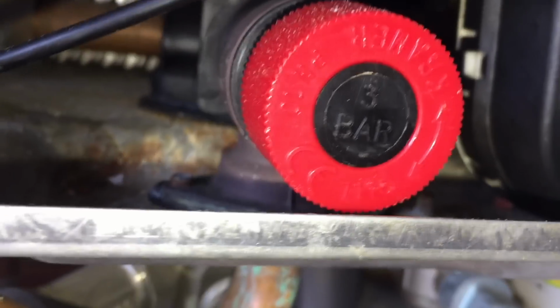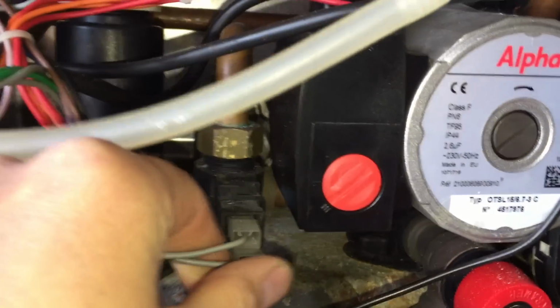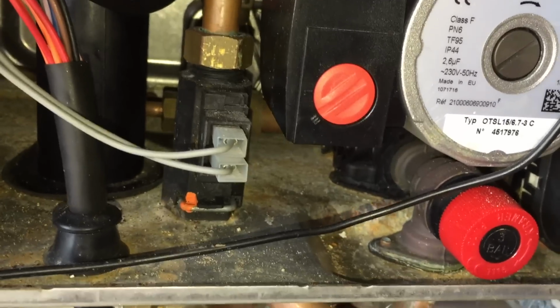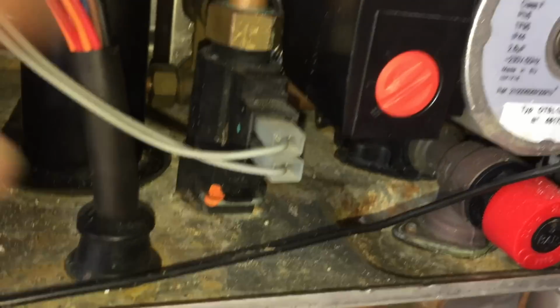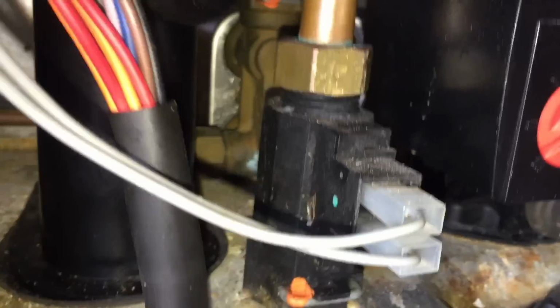Right, let's have a look in here. Is that a flow sensor there? I don't think so, that's a PRV. The pipe goes onto the plate, plate's back there, plate's in that hole there, we can see it. So there's our 2-wire domestic hot water flow sensor. It's got 2 wires, it's just a switch, guys.